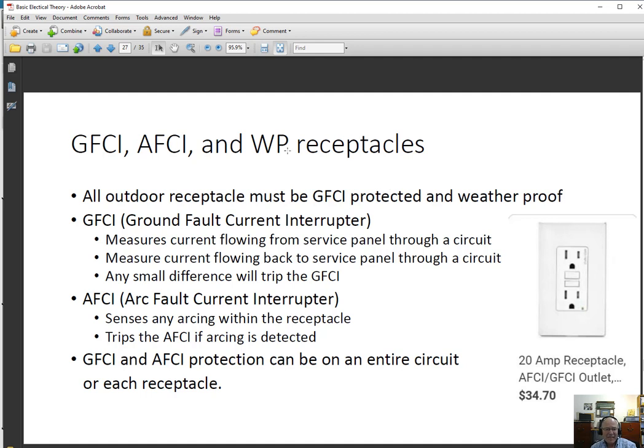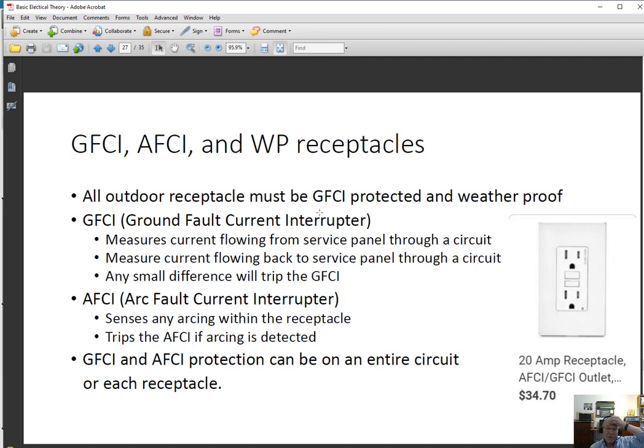Any outdoor receptacle must be GFCI protected and also weatherproof. Weatherproof is a designation for both the receptacle and the enclosure. The best weatherproof enclosure is recessed into the wall with a gasketed cover — you lift the cover, and whatever you plug in goes inside that recess. There are others that are not recessed but have covers over individual receptacles. Whatever you do, it has to be weatherproof.